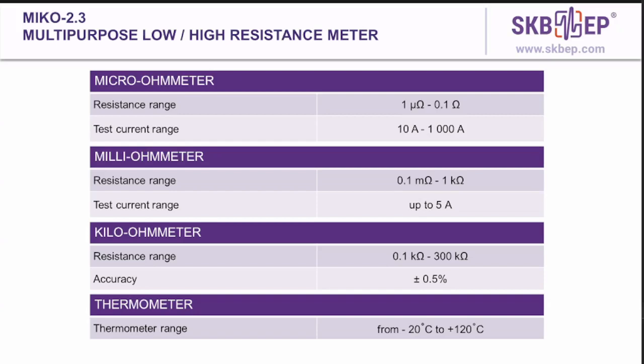The application areas, they are in a micro-ohmmeter mode. You can measure active resistances of old switching equipments with oxidized contacts. When it's switched to milliohmmeter mode, you can measure resistance in circuits with medium and low inductance. In a kiloohmmeter mode, you measure resistance of voltage dividers, ballast, shunt, and other resistors. And as I said, the thermometer can be used for windings, oil, and air temperatures.